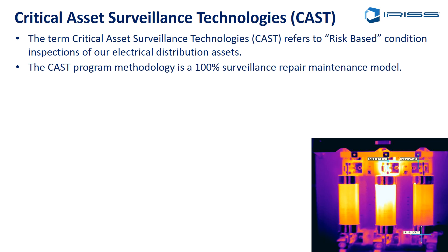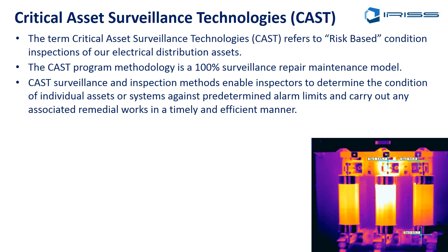We're going to inspect the equipment routinely and then react to the details of those inspections. CAST surveillance and inspection methods enable inspectors to determine the actual condition of the equipment against any predetermined alarm limits — whether that's a maximum temperature on an electrical connection or vibration limits on a mechanical generator system. As long as you understand those predetermined alarm limits, we can effectively carry out any maintenance needed in a timely fashion.